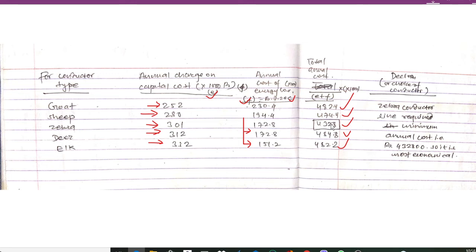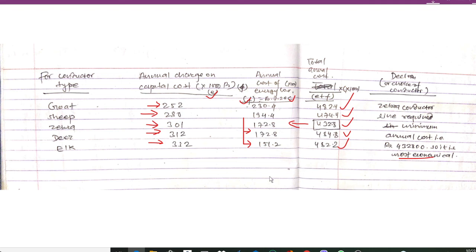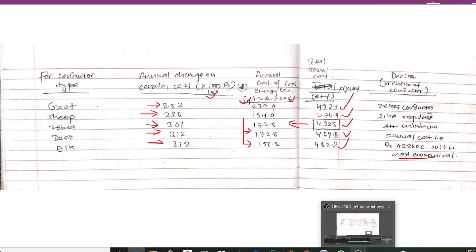Comparing all values, 432.8 is the minimum total annual cost, which corresponds to the Zebra conductor. Therefore, the Zebra conductor requires the minimum annual cost of 432,800 and is the most economical. We choose Zebra conductor as the most economical option. Thanks for watching — please don't forget to subscribe to my channel.